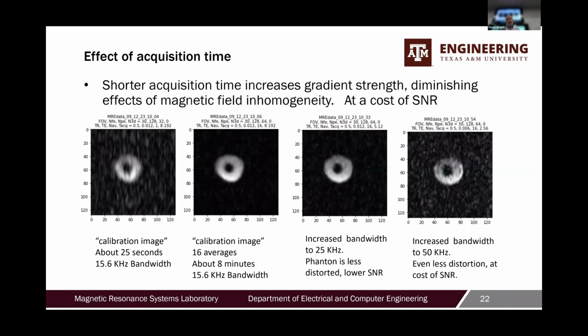So the effect of acquisition time. Here's a 25-second calibration image, 15 kilohertz bandwidth, just a test tube with a plastic bolt in the middle. 128 by 32, so very low resolution. Half a second TR, 12 millisecond TE, 15 kilohertz bandwidth, 8.192 milliseconds acquisition window. If we run more averages, we get a pretty good signal to noise. It's kind of lopsided. Where does that come from? Because it's a test tube.